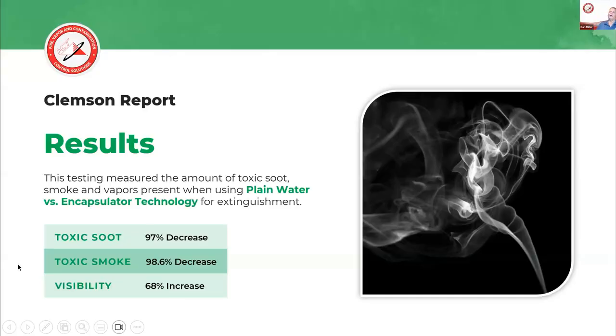The results of using F500 in that environment can result, in a lab at least, in up to a 97% decrease in toxic soot production, 98.6% decrease in toxic smoke production, and a visibility increase of 70%. You don't get quite those results in the field because it's not a perfect application, but we do have lots of testing to show that this is happening across the board with all of the VOCs coming off of that fire, the cancer-causing VOCs, the VOCs that make the fire grow.